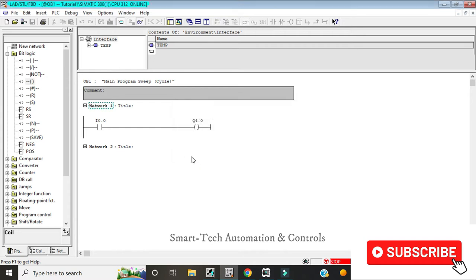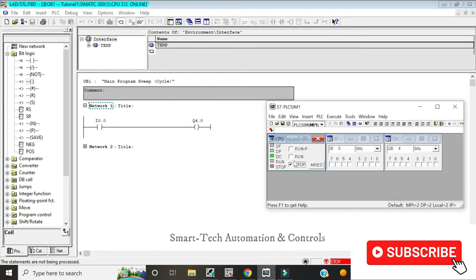So I'll download the program to my simulator. Then I turn on my simulator and I put it on run mode. So my input is I0.0. If I give my input a signal, you can see that we get an output at Q4.0. And if I withdraw the signal, the output goes off. So that's how a normally open contact and a coil work.